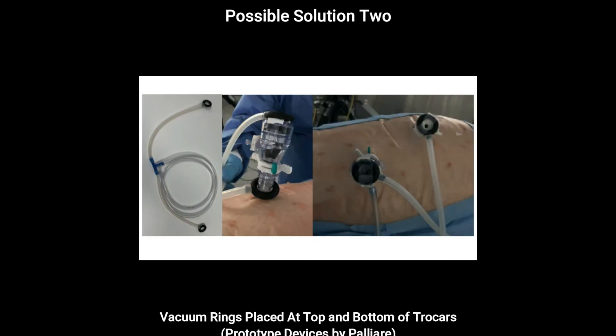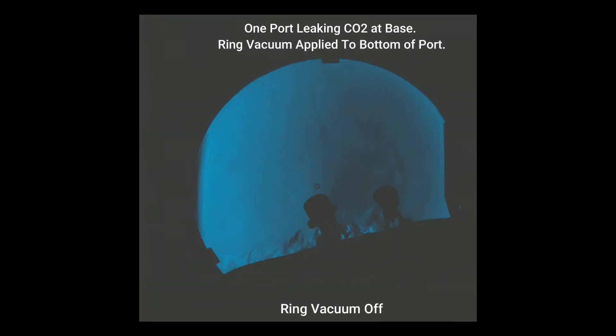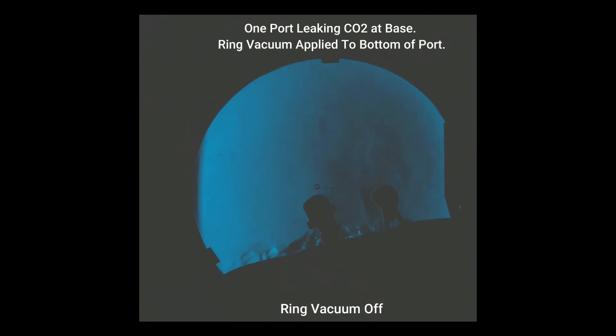Another approach could be to place vacuum rings at the top and base of the trochars to manage whatever leakage occurs. Here we can see the effect of switching on the vacuum via a ring placed at the bottom of the trochar in managing an incisional gas leak.